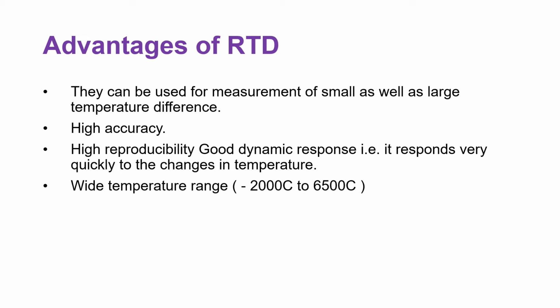Now the advantages of RTD. First, they can be used for the measurement of small as well as large temperature differences. Then next, high accuracy. Then high reproducibility. Then good dynamic response. Then next, wide temperature range, that is from minus 200 degrees Celsius to 650 degrees Celsius.